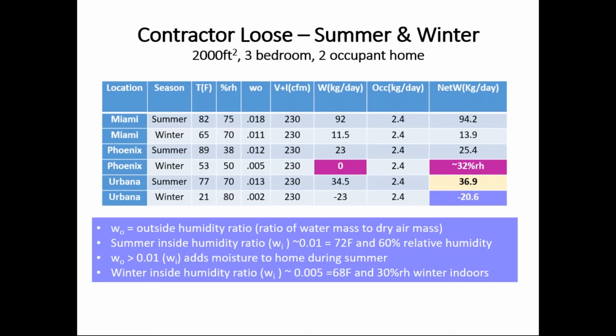Miami, for contractor loose in the summer, instead of 0.013 as we have in Urbana, the average outside humidity ratio is about 0.018. Almost 2% of the air is water in Miami at that time of year. And for a loosely built home, 6 ACH at 50 pascals and 2 occupants, we have about 94 liters of dehumidification capacity that's needed in order to keep the inside of the house at about 72 degrees Fahrenheit with 60% humidity.